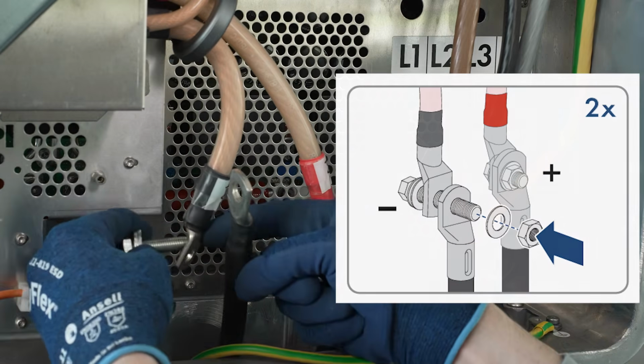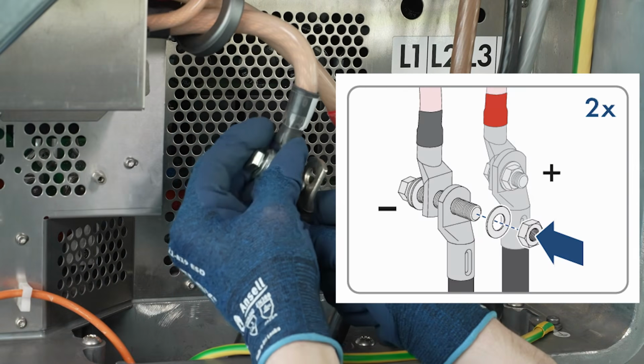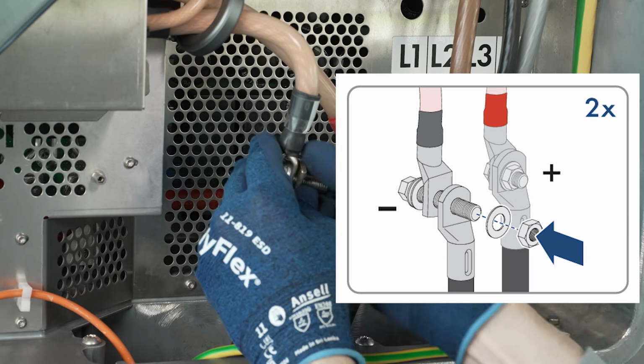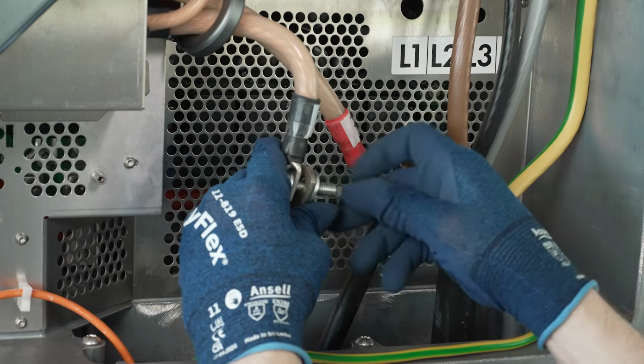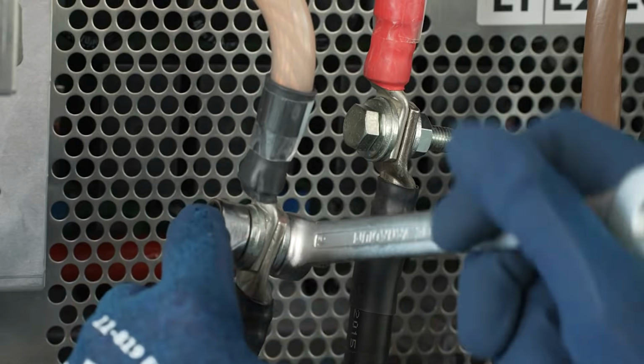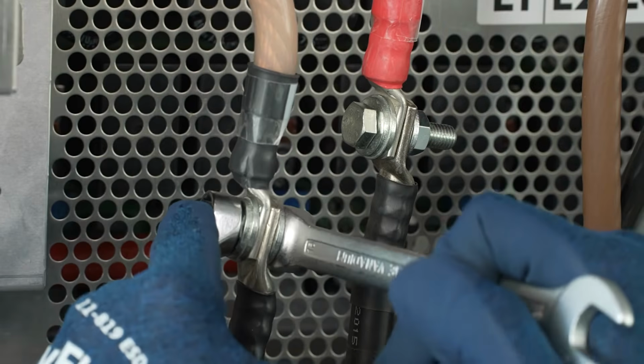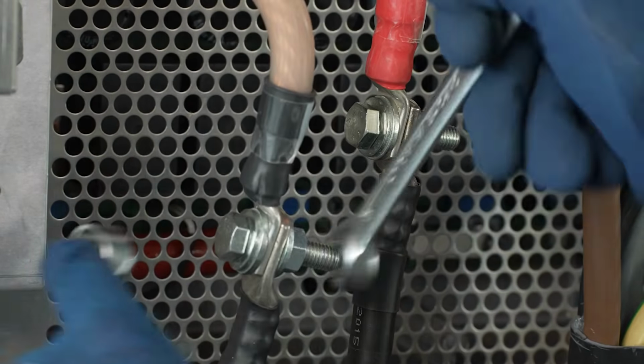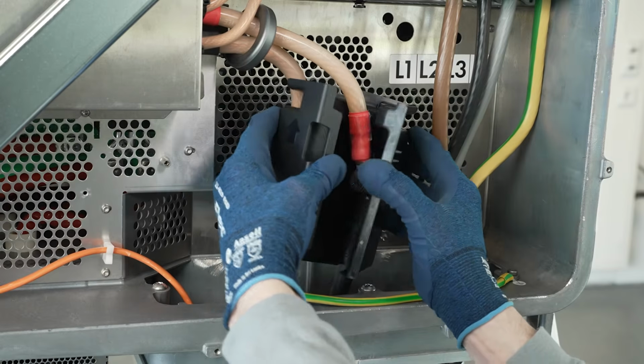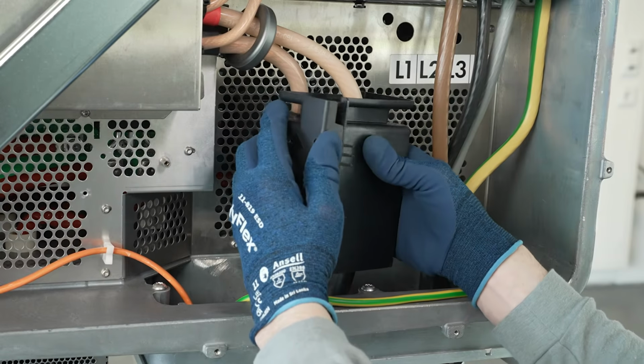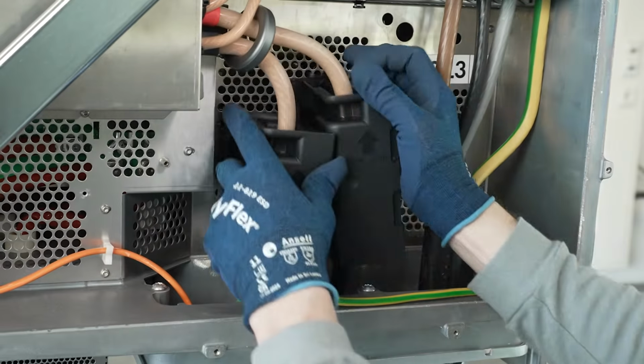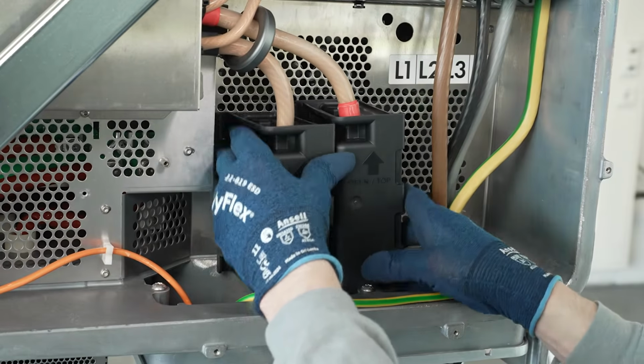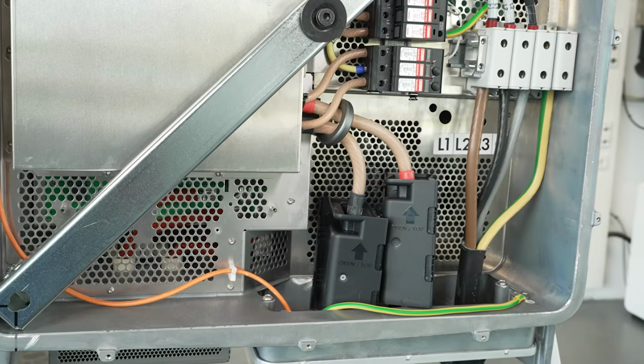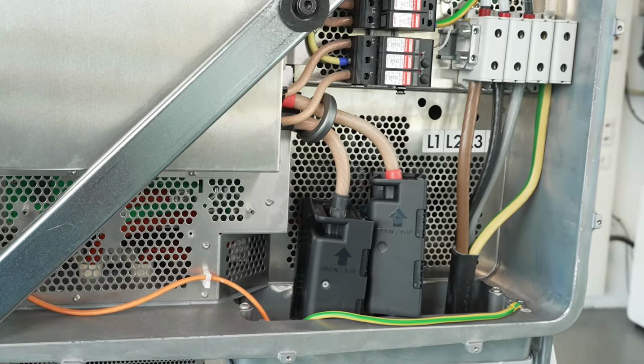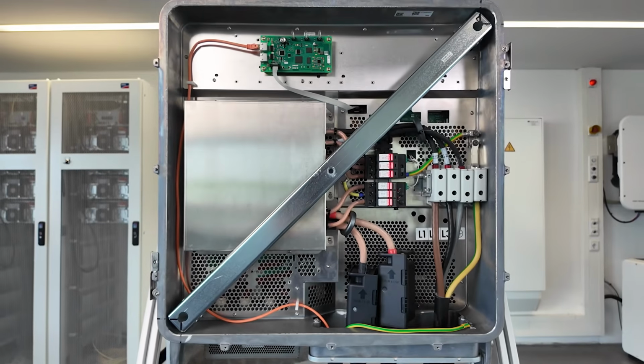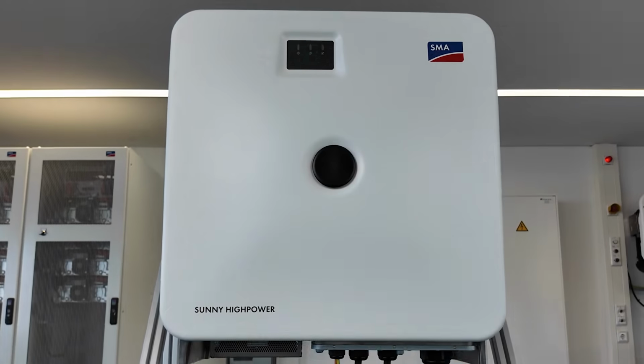Now we connect the DC cables to each other. To do this, we insert the combination screw from the back through the round holes of the cable lugs and secure it from the front with a washer and hex nut. We tighten the connection with a torque wrench, making sure to observe the correct polarity. Finally, we place the touch protection elements around the cable lugs and snap them together until they audibly click into place. With that, the DC connection is complete. After a successful connection, the device is ready for commissioning.